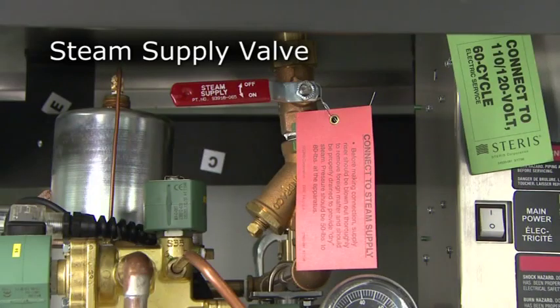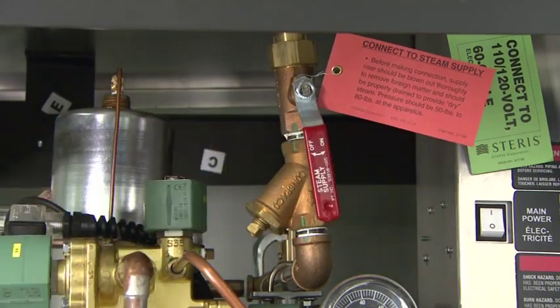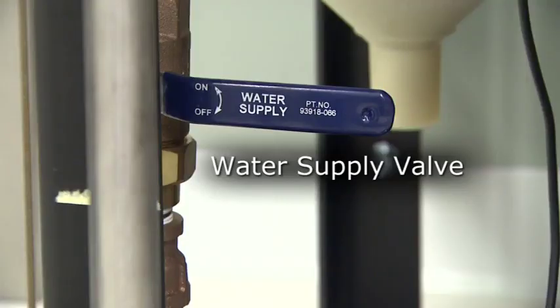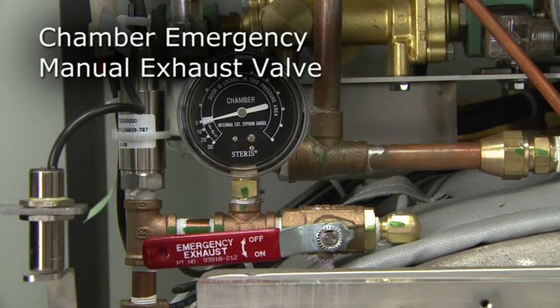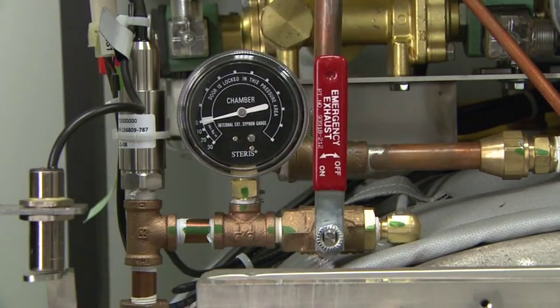The steam supply valve is located behind the side access panel or within the wall enclosure above the chamber. Ensure this is in the open position before trying to operate the sterilizer. The water supply valve is located behind the side access panel or within the wall enclosure below the chamber. Ensure this is in the open position before trying to operate the sterilizer. The chamber emergency manual exhaust valve is used only in emergency situations. This valve is to be left in the closed position for normal operation.